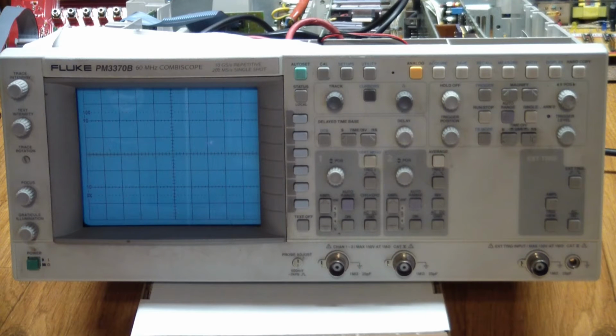Somehow it is discharging. And the best way to do a corona hunt is, and follow this closely, wear protective glasses, keep your face a respectful distance from the top of the instrument, and turn off the room lights, and then turn on the instrument. And that's exactly what I did. And here's what I found.